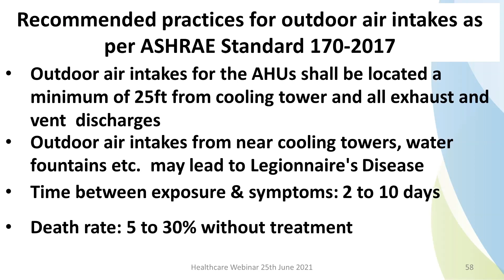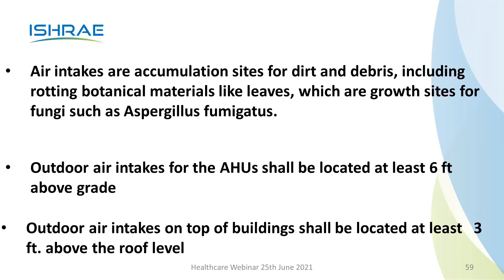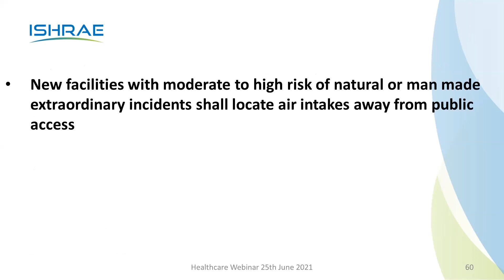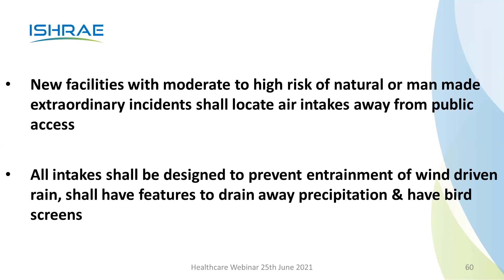Outdoor air intakes. Actually, this happens especially when you've got intake louvers and there is no drain from that intake louvers. If you see these intake louvers, it is always full of muck. So well-designed intake louvers which drain out water, that's very important. Outdoor intakes for AHU shall be located at least 6 feet above the grade, that is the floor level. Outdoor intakes on top of building shall be at least 3 feet above the roof level. The new facilities with high risk of natural or man-made extraordinary events shall be located with intakes away from public access. All intakes shall be designed to prevent entrainment of wind-driven rain, shall have features to drain away precipitation and have bird screens. This is what we talked about. The intake louvers should have a draining facility.